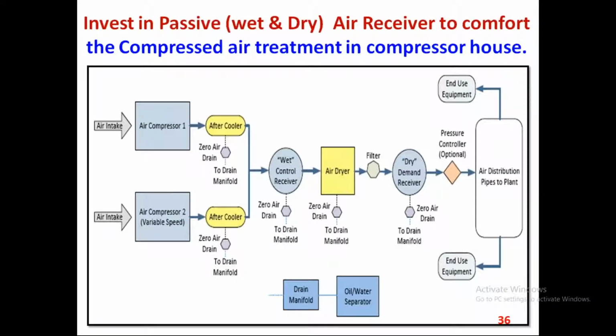That is why, when you go to an industry, you always suggest they go for 2 types of receiver. They call it a wet receiver or dry receiver, or you can call it a demand receiver or a control receiver. This control receiver is to control the cut-in and cut-out for the compressor, whereas the demand receiver will take care of the process.